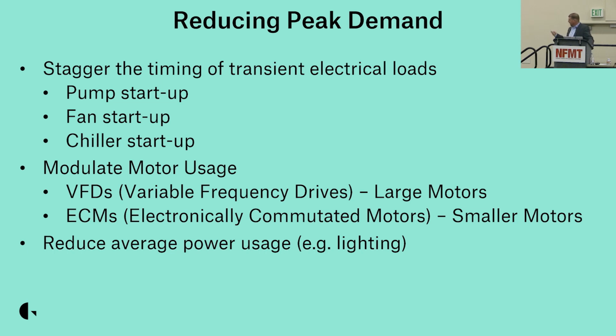Modulating motor usages, VFDs, ECMs, those are for like smaller motors. But the VFDs, this is a facility that did a complete retrofit, a 20-year upgrade on the chillers. It had solid state electrical components in it. When it came on, it pulled in the electrical contactor and just slammed it on, 0 to 100. The outside air fan of the building, 0 to 100 when it ran. Just by putting VFDs on the chillers and ramping it up, and putting VFDs on the outside air fan, it allowed us to modulate, so now we're not using 100% all the time when we needed it. And just the startup alone of the equipment, putting the drives on, we were able to provide a payback that showed just starting it up saved energy.